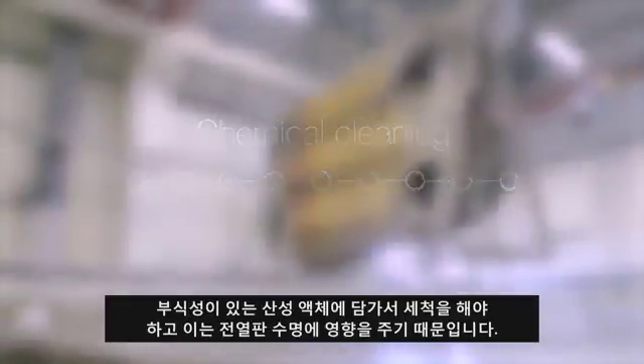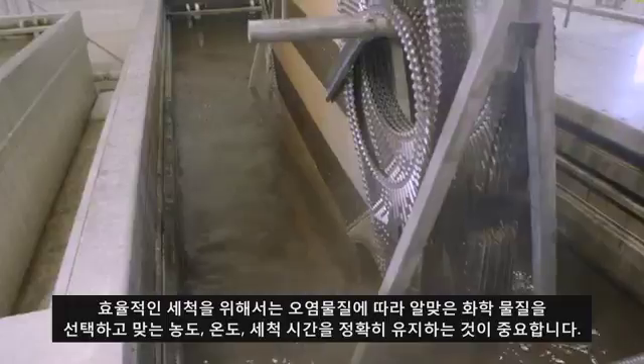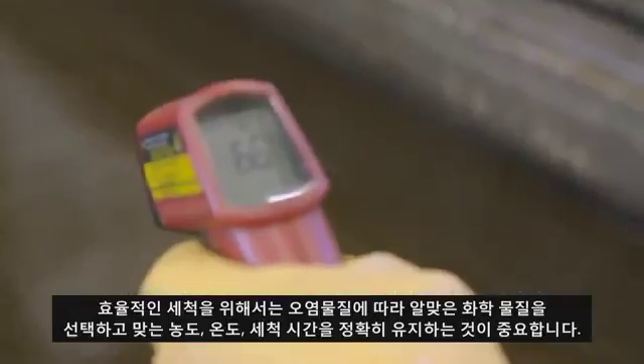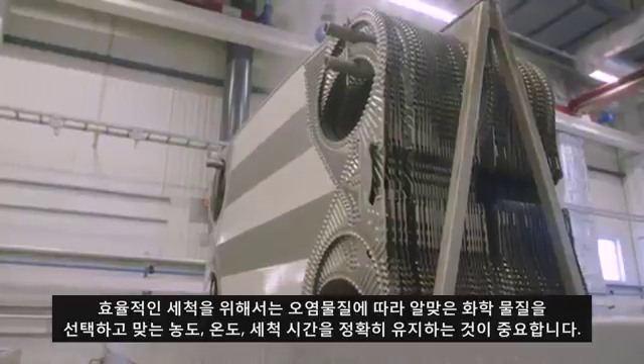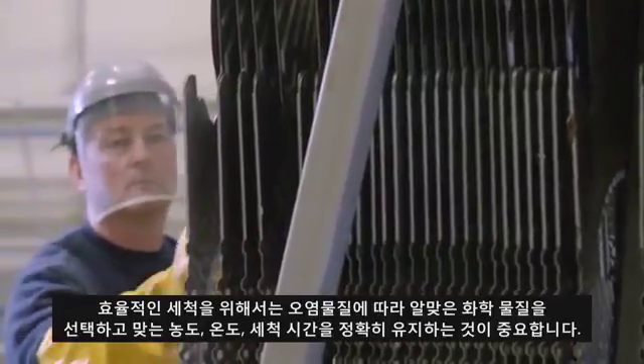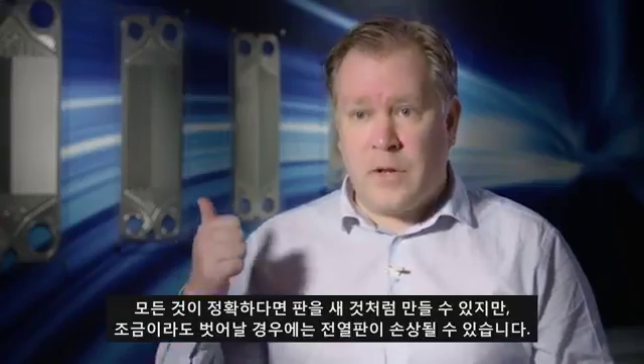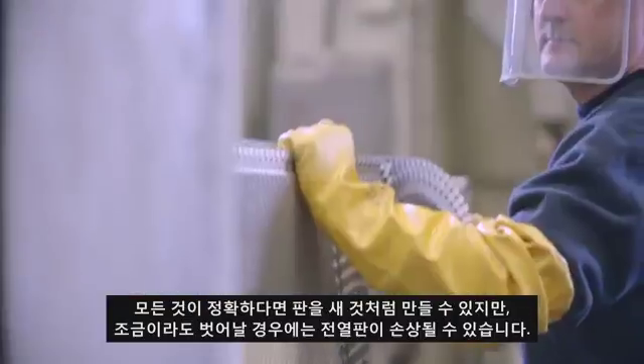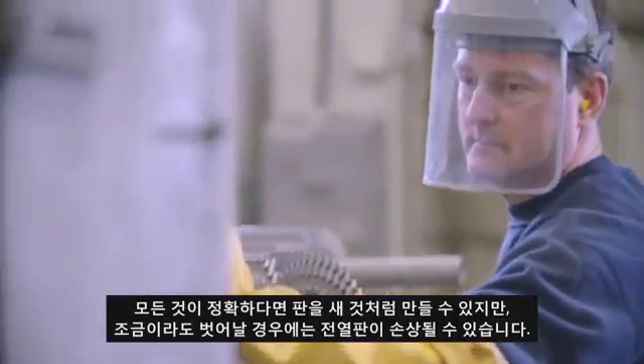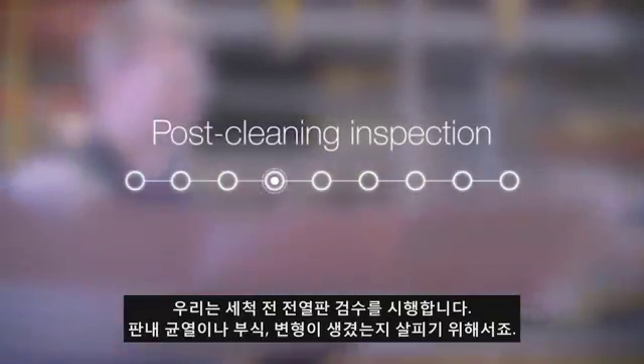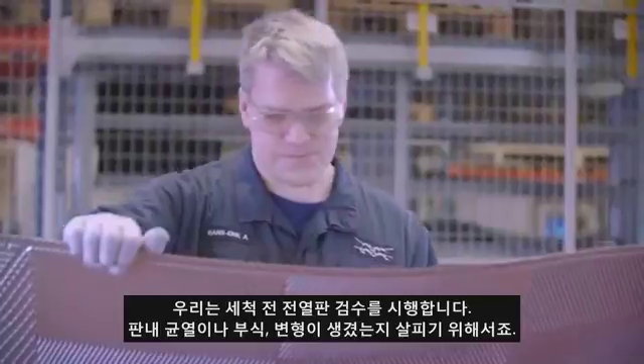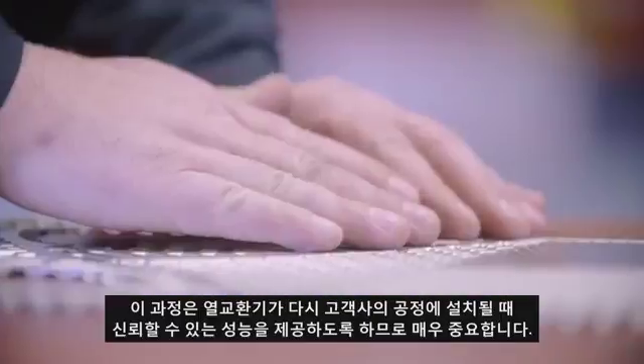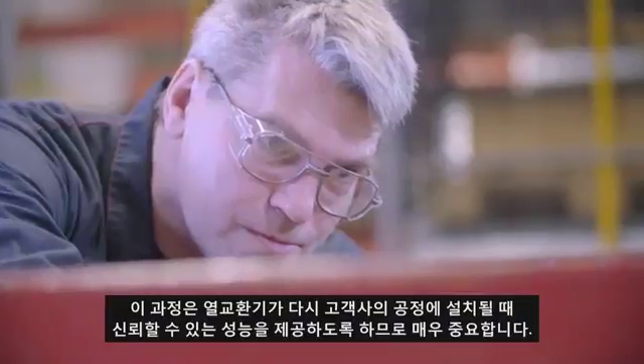We clean the plates by submerging them in a caustic and an acid bath. It's important to get the right chemicals, concentration, temperature, and duration in order to have an efficient cleaning process. If you get that right, you get plates in as good as new condition, and if you don't get it right, you risk damaging the plates. We do post-cleaning inspection in order to identify signs of cracks, corrosion, and deformation. And that's important because that helps you to improve the reliability of the equipment when it's back in operation.